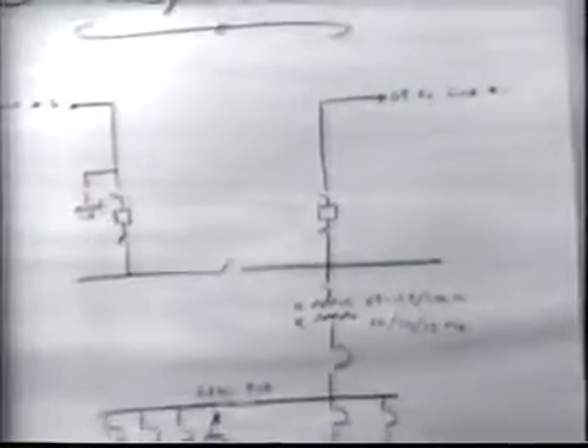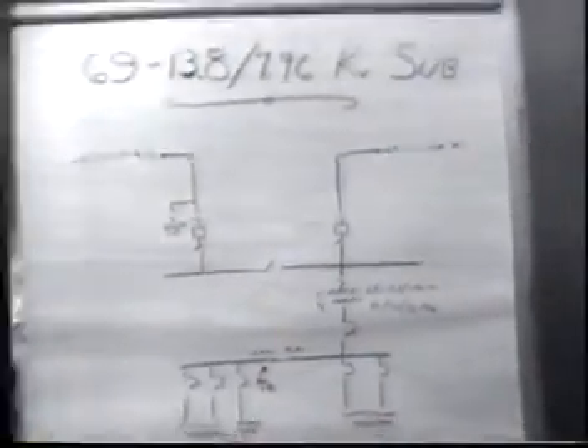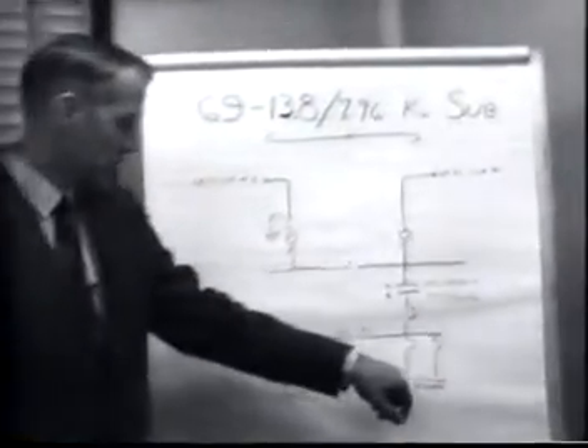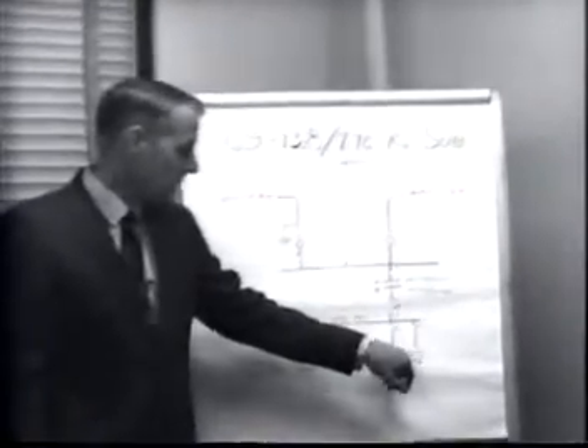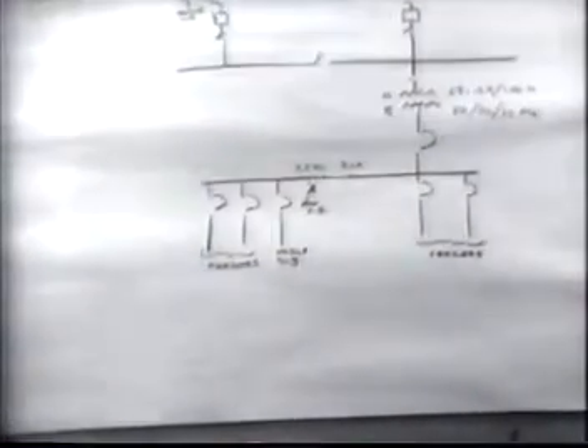The secondary side of this transformer is connected to 15 kV metal-clad switchgear to 2 bus sections, and from these sections we have radial feeders extending out into the suburban area. Since we have a single transformer, if we were to lose this transformer, or if we wanted to take it out for maintenance, unless special provisions were made, we'd be kind of out of luck.